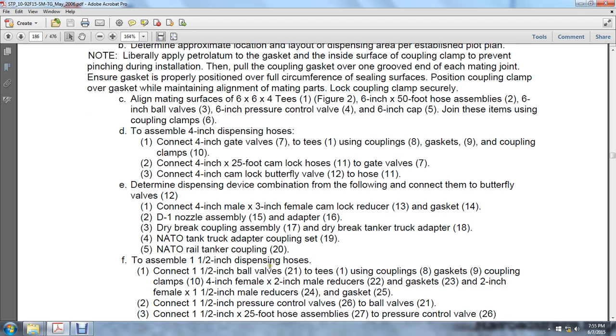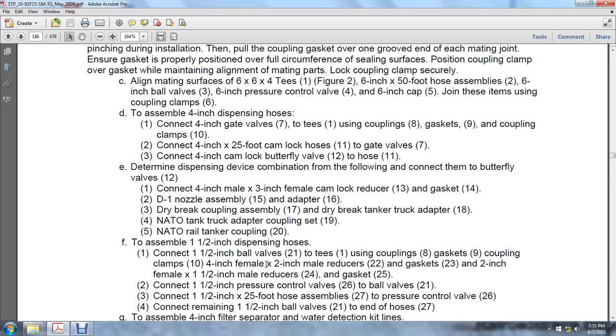To assemble the 1.5-inch dispensing hoses, connect the 1.5-inch ball valves (21) to the 2 tees (1) using gaskets (8 and 9) and coupling clamps (10). Add the 4-inch female, 2-inch male reducers (22), gaskets (23), the 2-inch female, 1.5-inch male reducers (24), and gaskets (25). Connect the 1.5-inch pressure control valves (26) to the valves (21). Connect the 1.5-inch 25-foot hose assembly (27) to the pressure control valve (26). Connect the remaining 1.5-inch ball valves (21) to the end of the hose (27).